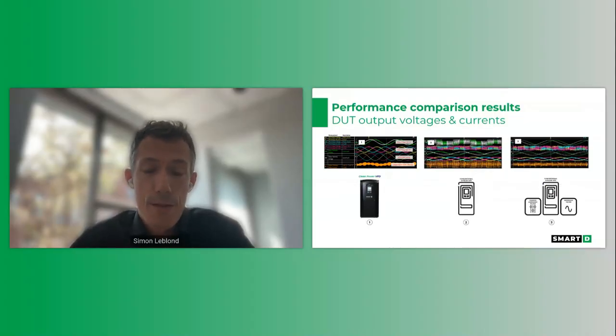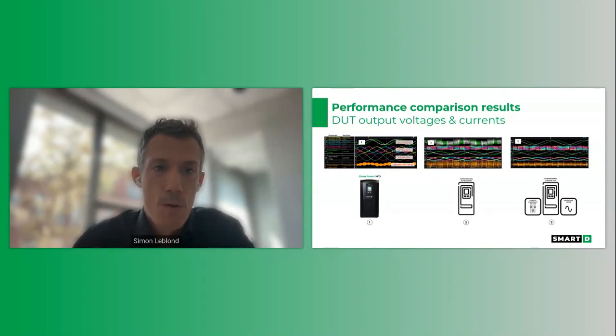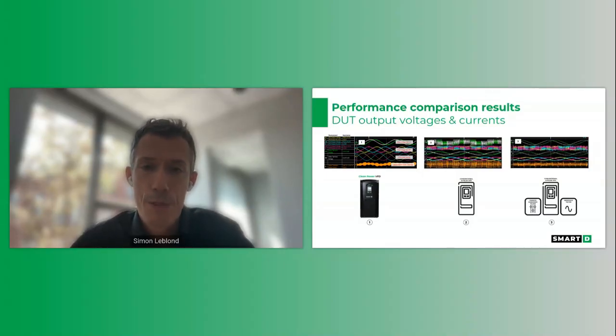So the first thing you can see is that there's a clear difference in the signal going to the motor. Just visually, you can see how the motor VFD voltage and VFD current are significantly different from the conventional 6-pulse VFD. You're not having that square signal that you talked about that is generated by the PWM. So even before we do further testing, we can assume that a lot of the PWM damage you talked about would be mitigated. Same thing for the common mode voltage, where you can see that it is much smaller in amplitude. And when we compare the left side of the screen with the right side, we're also seeing that even though the filters are helping quite a lot, we're still seeing a much nicer signal, for example, on the VFD voltage. But let's dig a little bit more into those data and results.